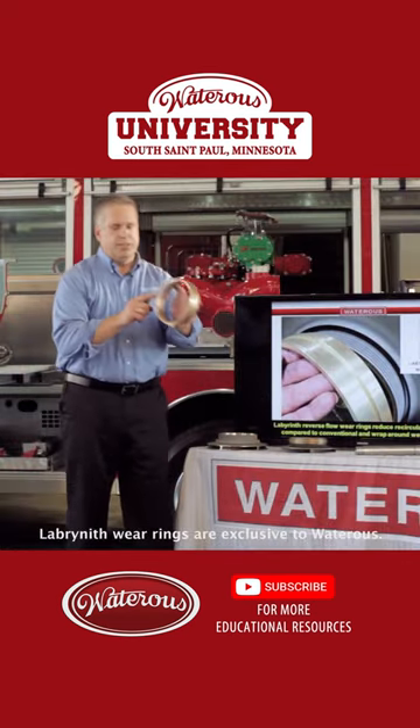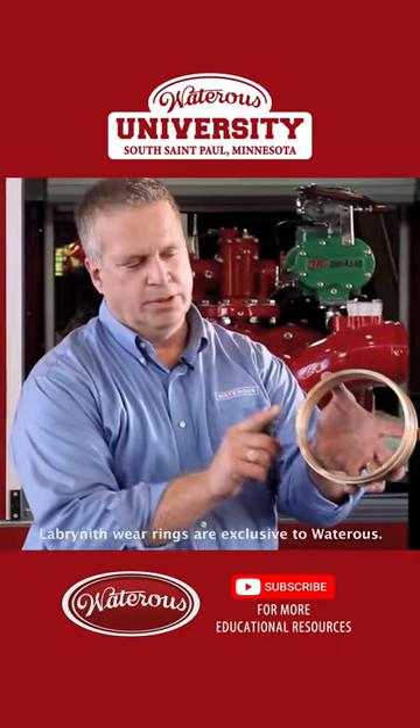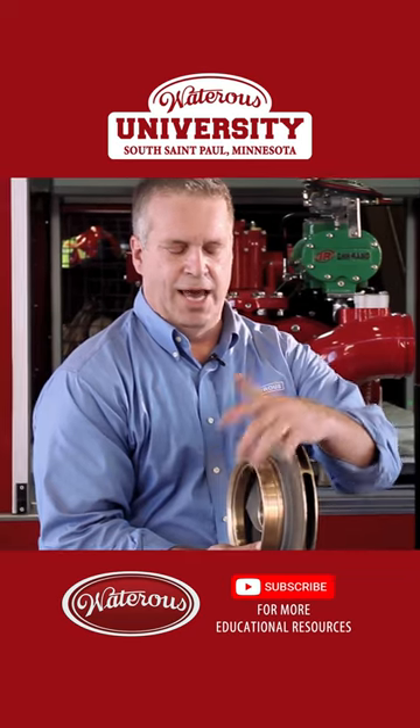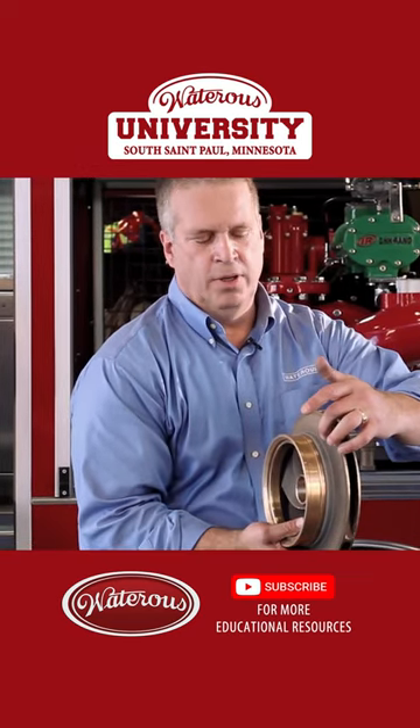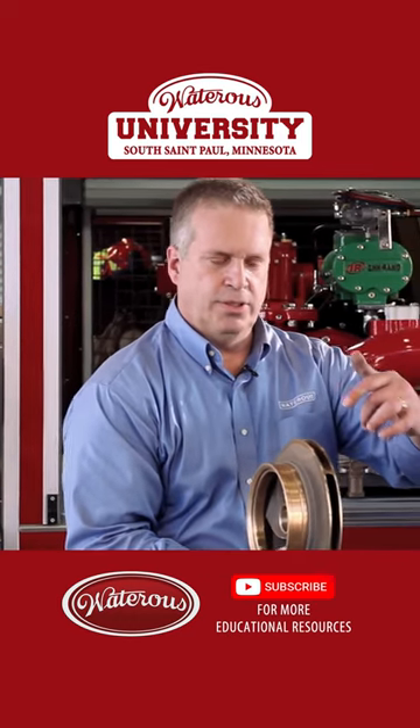The wear ring actually has a stub that sticks out of one side. When the water wants to circulate back into the eye of the impeller, it has to come down the front shroud, on the outside of the recess, on the outside of the wear ring, back towards the impeller, down, then through the clearance back into the eye.